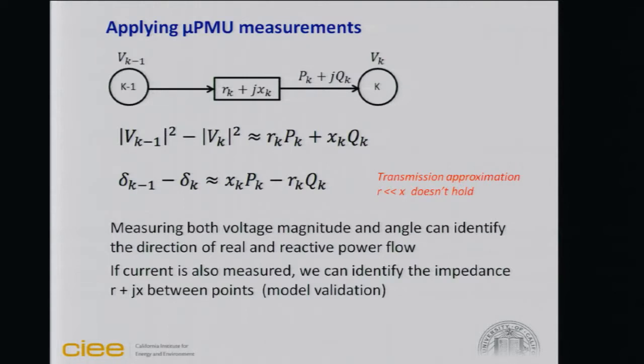The approximations that work for the transmission system are wrong in distribution, because in transmission you assume that the resistance of a line is very small compared to the inductive reactance. That's wrong in distribution, which makes the math more complicated. It's also more complicated because you have three phases that aren't all behaving the same way as one assumes in transmission. So these are still approximations.